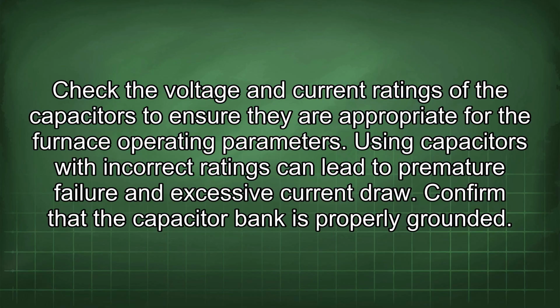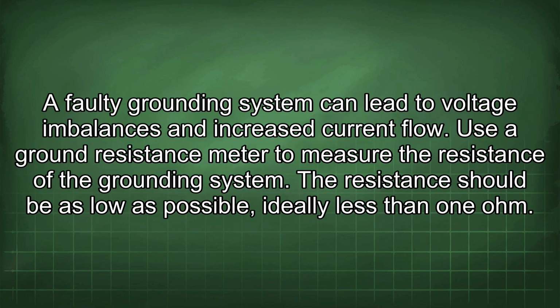Confirm that the capacitor bank is properly grounded. A faulty grounding system can lead to voltage imbalances and increased current flow. Use a ground resistance meter to measure the resistance of the grounding system. The resistance should be as low as possible, ideally less than 1 ohm.